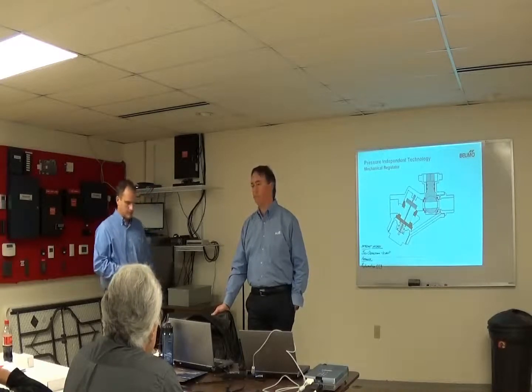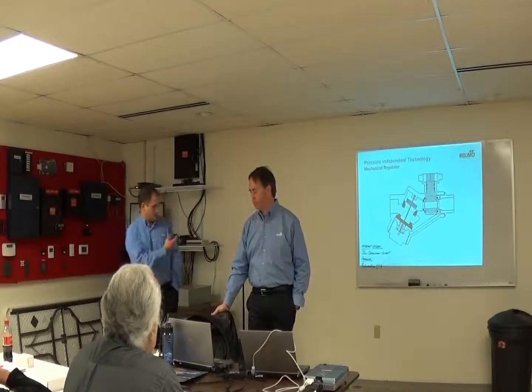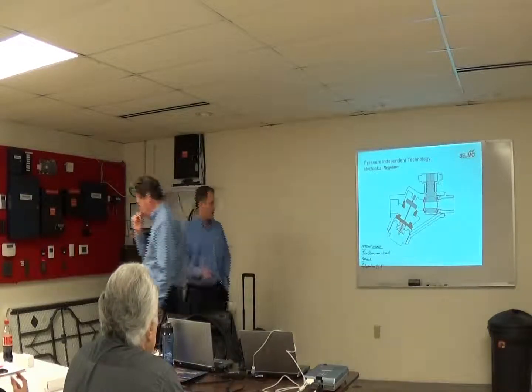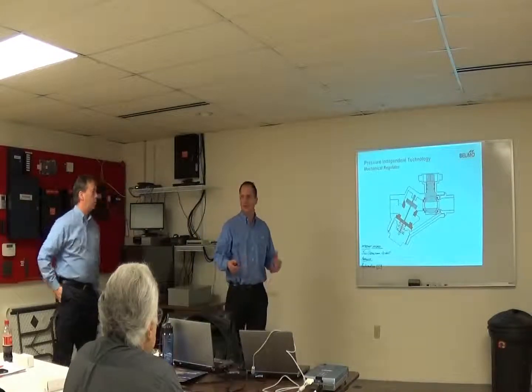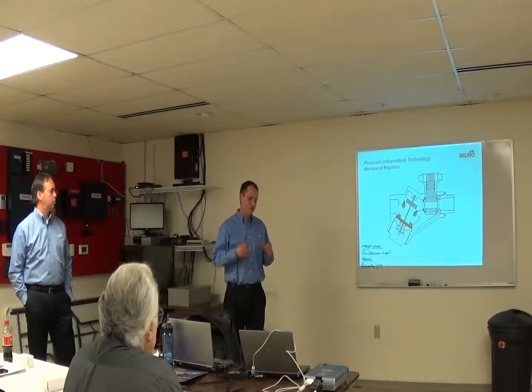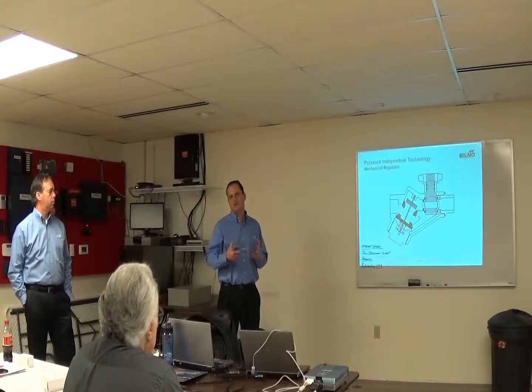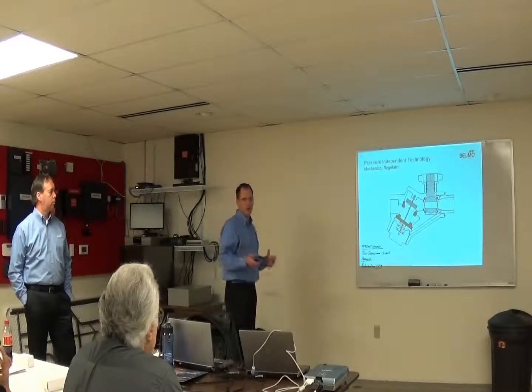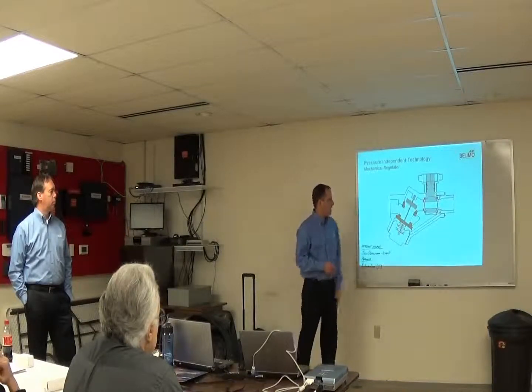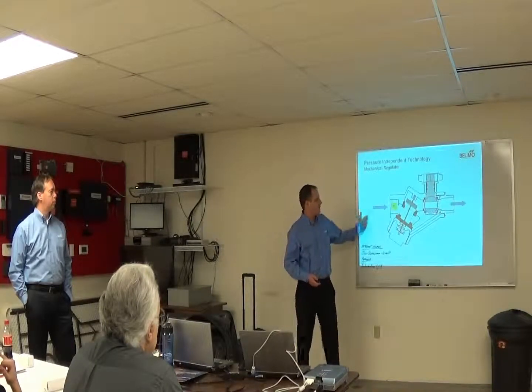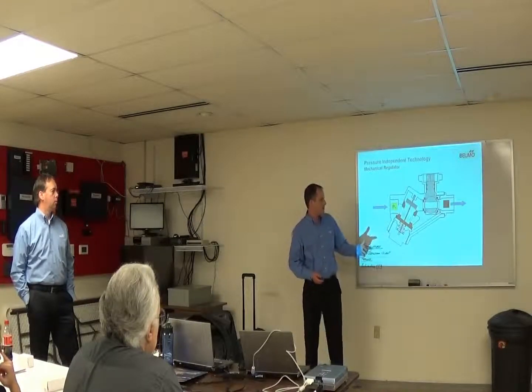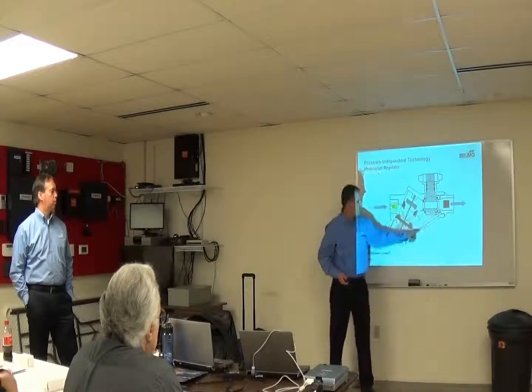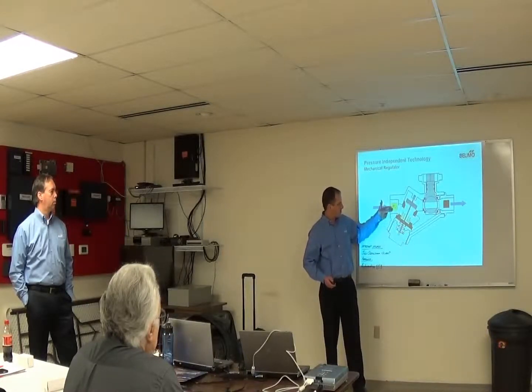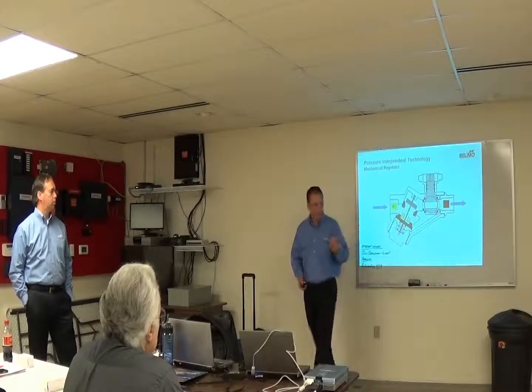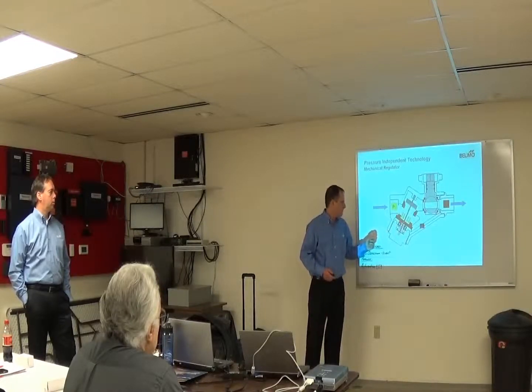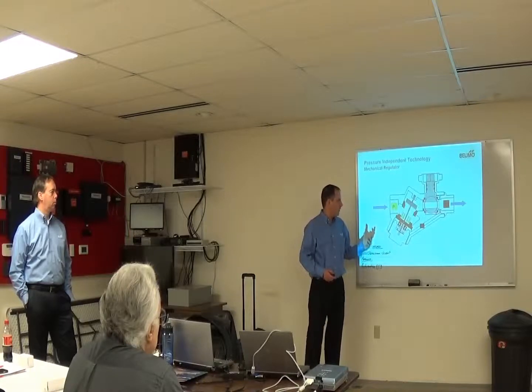And that's what we do here on our mechanical pressure independent valve, if you guys aren't familiar. Everybody else will make something similar. A lot of people used to make pneumatic valves or pneumatic actuators, so their design looks more like a pneumatic design. But basically you've got an inlet and an outlet. Water flows from left to right in this case. You've got a pressure upstream, pressure downstream. We've got a channel for our downstream pressure. Our upstream pressure is sensed here. And then we've just got a spring with a known ability to absorb the pressure differences.